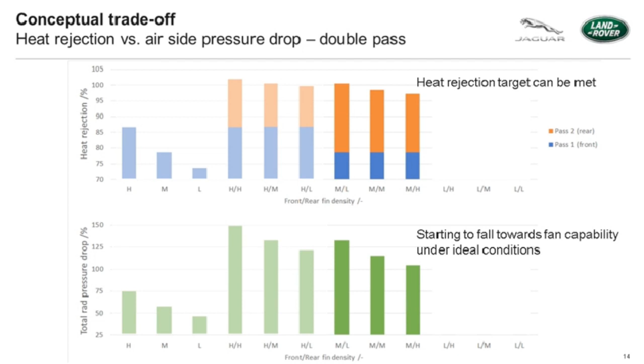Now we see that the duty on the front pass is reduced to about 75%, and the airside pressure drop has improved on a back-to-back basis. The better thermal balance is good because it reduces the thermal shock, and therefore we can improve the durability of the radiator pack overall. But this conceptual trade-off analysis gives us good insight into the trade-off between heat rejection and airside pressure drop.